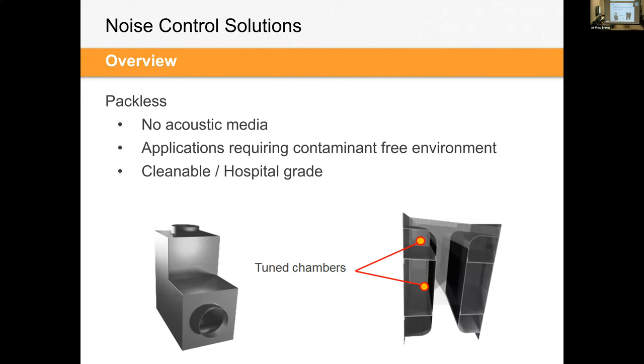So these are empty void metal chambers that sound waves will propagate into and then dissipate as they enter these chambers. We use these a lot for things like fume hoods, lab exhausts, anything with chemicals within it, because you can't really have acoustic media in those chambers. We're actually seeing more of a need for kitchen exhaust of all things, where you have a fume hood and, you know, grease duct. And if you're ever designing a system like that, those can be extremely loud.